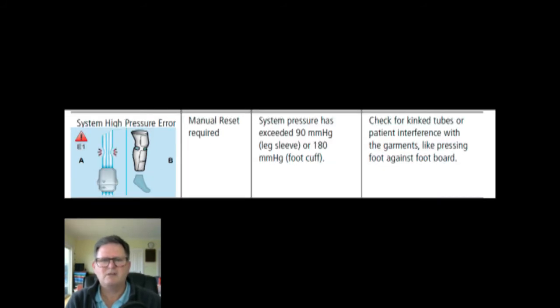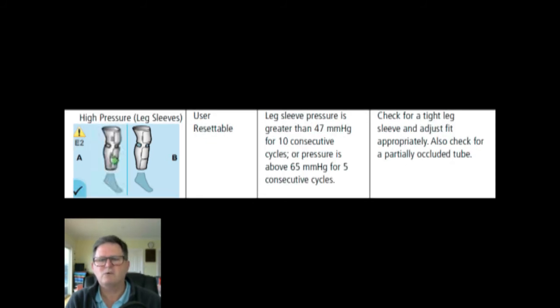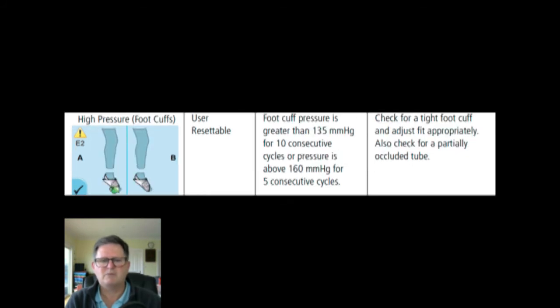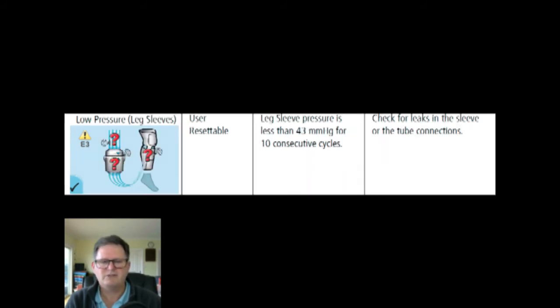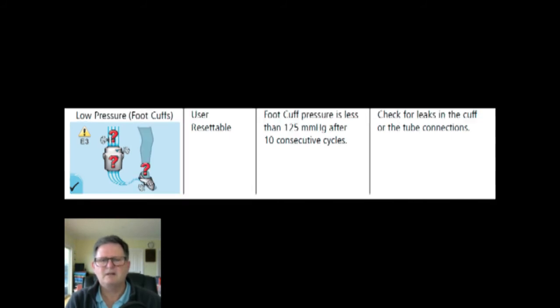They're quite good, they show the picture you get on the screen, give you an idea of which error it is, what you should be doing, and what may have caused the problem. Typically it'll be someone hasn't plugged the hose in properly, or there's a leak in one of the hoses, or maybe one of the sleeves is faulty.